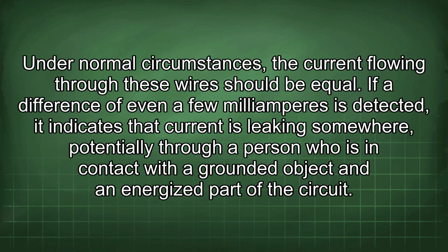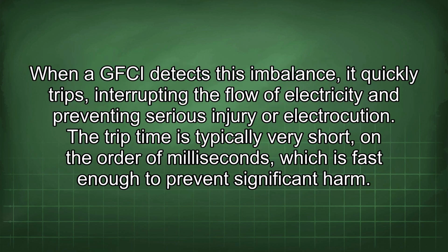Under normal circumstances, the current flowing through these wires should be equal. If a difference of even a few milliamperes is detected, it indicates that current is leaking somewhere, potentially through a person who is in contact with a grounded object and an energized part of the circuit. When a GFCI detects this imbalance, it quickly trips, interrupting the flow of electricity and preventing serious injury or electrocution. The trip time is typically very short, on the order of milliseconds, which is fast enough to prevent significant harm.